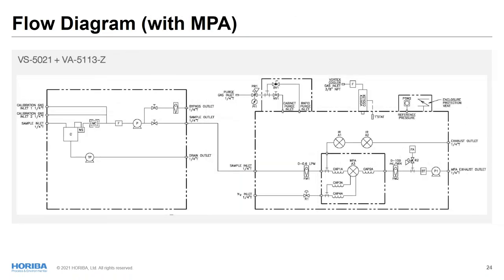This is another flowchart showing the wall mount sample system and the wall mount VA-5000 with MPA-02 analysis. As you can see, the wall mount sample system design is the same as the one for NDIR. And the analyzer is this one, just the Z-purge version. You can see a purge gas inlet, right, and the vortex cooler inlet here, and here's the vent. Other than that, basically the inside of the design is the same.